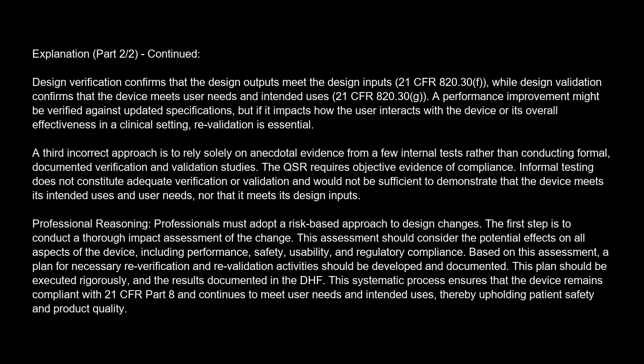A third incorrect approach is to rely solely on anecdotal evidence from a few internal tests rather than conducting formal, documented verification and validation studies. The QSR requires objective evidence of compliance. Informal testing does not constitute adequate verification or validation and would not be sufficient to demonstrate that the device meets its intended uses and user needs, nor that it meets its design inputs.